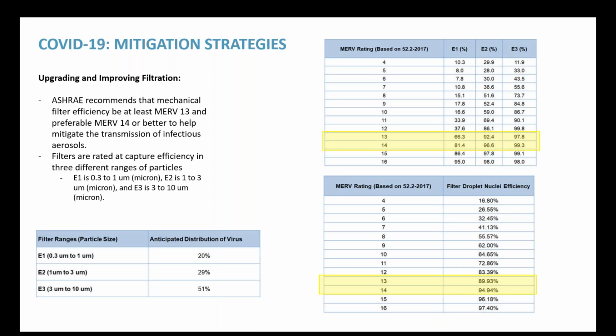So what ASHRAE did is they looked at what they considered to be the anticipated distribution of the virus. They used historical information about viruses that we know about, like influenza, to figure out what droplet sizes we are actually talking about in the air, and what fraction of those there are. So you can see 20% at the smallest sizes and 51% distribution at the largest sizes. Then you look at the MERV ratings and figure out the different efficiencies of these MERV ratings. And you can start to see why the 13 minimum, 14 if you can do it, becomes important. Because at the smallest sizes, the E1 size range, when you go from a MERV 13 to a 14, you go from around 66% efficiency all the way up to 81%. So that's a big jump.